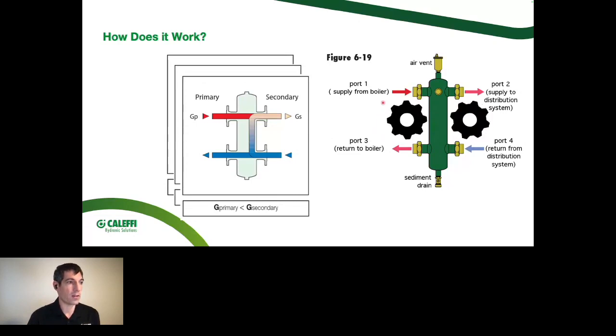So this could be a 20-degree delta T across the boiler heat exchanger, and this could be a 5-degree delta T across some fan coils or something like that. So even in a scenario where we're moving the same amount of BTUs out to the system, this could be spinning faster. That's one of the tricky things about primary secondary piping: the same flow rate on both sides, and you're also anticipating the same delta T, which is potentially possible, but probably not going to be the case most of the time. You might have a difference there, and primary secondary just quietly solves that problem.